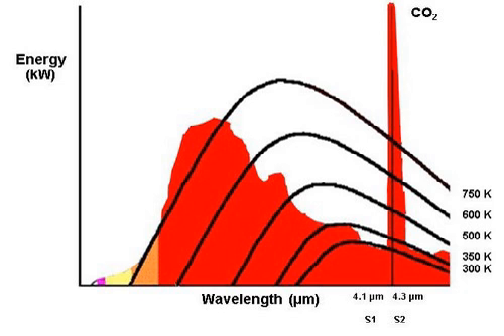A special frequency range is 4.3 to 4.4 micrometers. This is a resonance frequency of CO2. During burning of a hydrocarbon, for example, wood or fossil fuels such as oil and natural gas, much heat and CO2 is released. The hot CO2 emits much energy at its resonance frequency of 4.3 micrometers. This causes a peak in the total radiation emission and can be well detected.